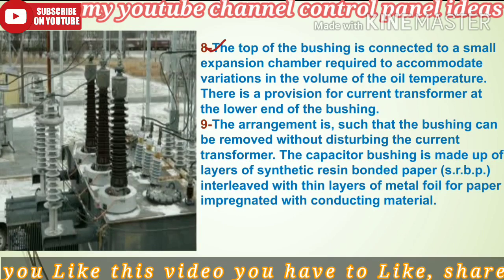Point 8. The top of the bushing is connected to a small expansion chamber required to accommodate variation in the volume of the oil with temperature. There is a provision for a current transformer at the lower end of the bushing. Point 9. The arrangement is such that the bushing can be removed without disturbing the current transformer.